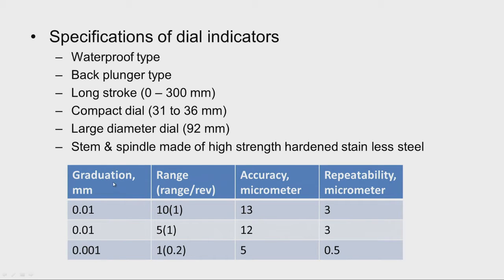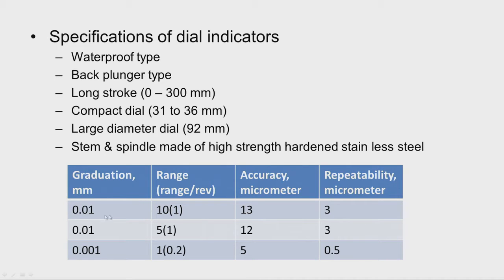Graduations are available in 0.01 mm and 0.001 mm, with ranges of 10, 5, and 1 millimeter. Per revolution, the range is 1 millimeter. The overall accuracy is about 13 microns for 0.01 mm graduation, and 5 micrometers for 0.001 mm graduation. Repeatability is 0.5 to 3 micrometers. Depending on our requirement, we select the appropriate dial indicator.